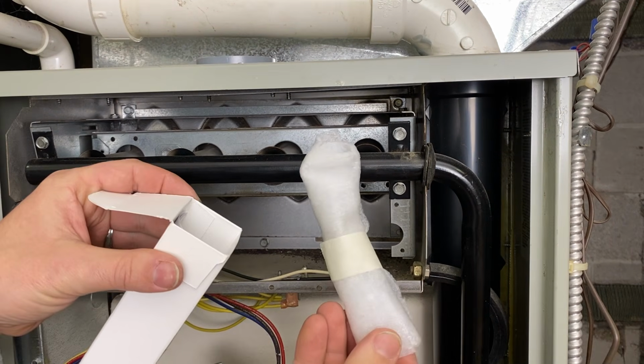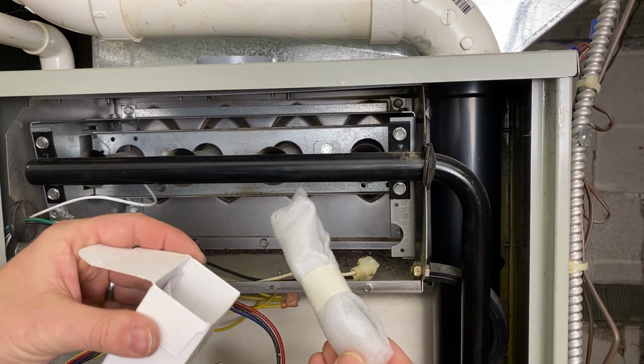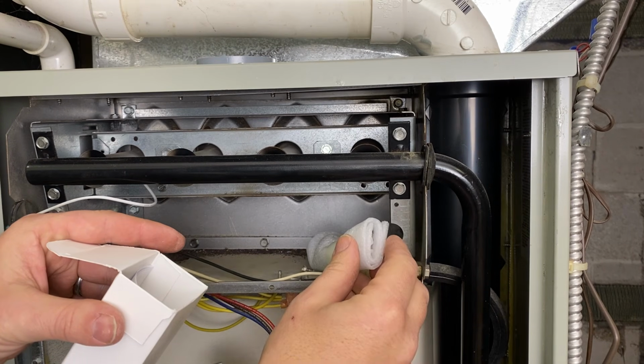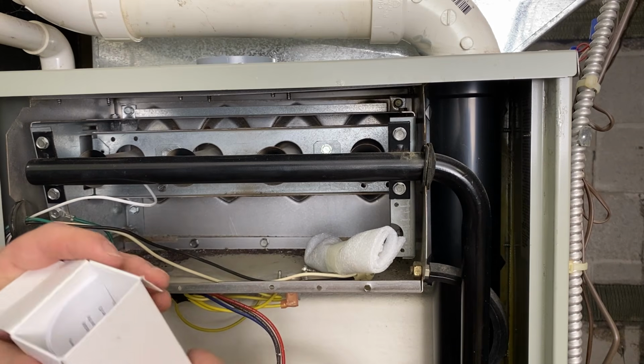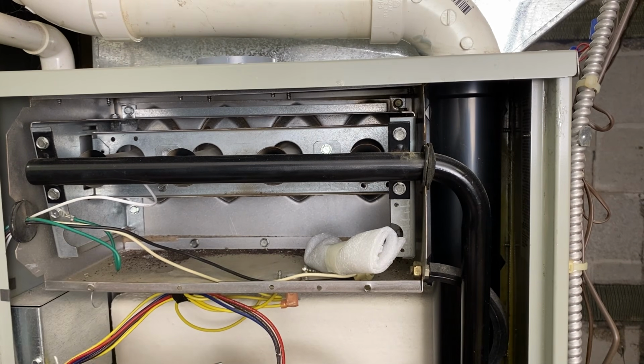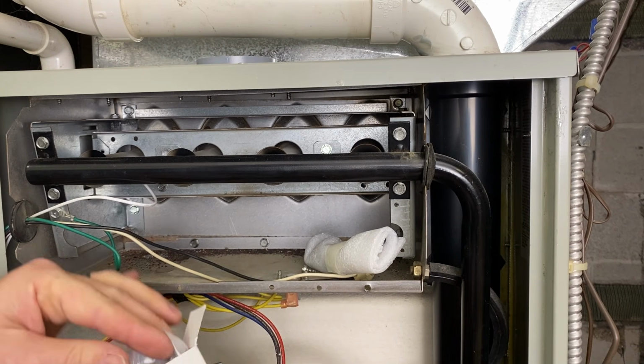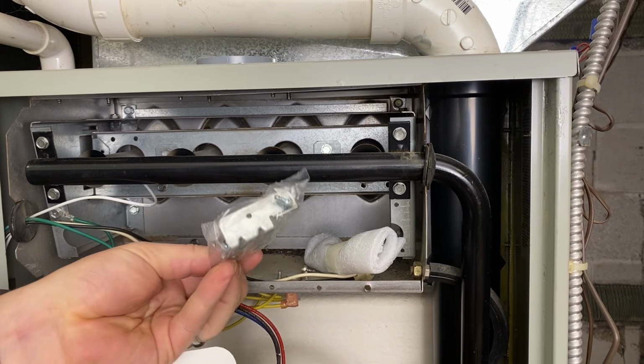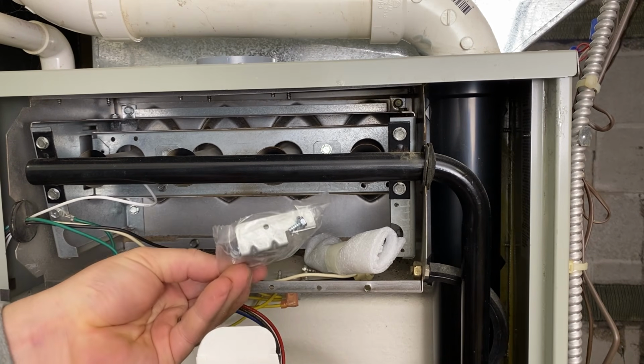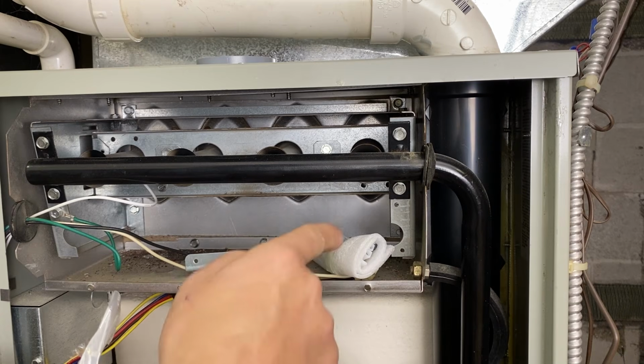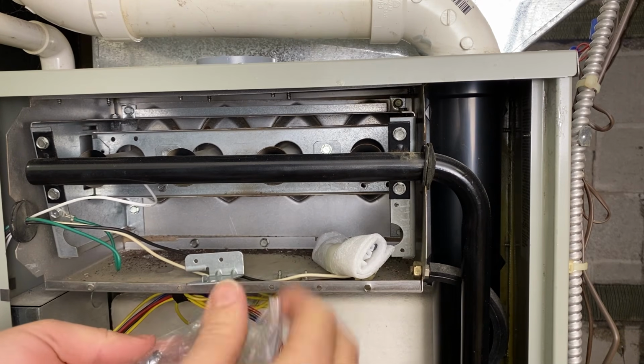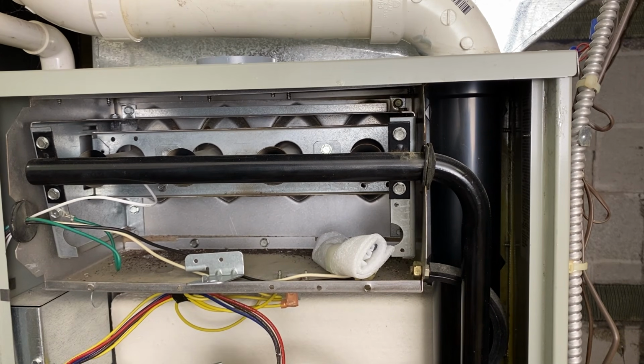So one thing to note with the hot surface igniter is that it is a very sensitive part. You don't want to touch it with your fingers to get any of the oils from your fingers on it, because it can actually cause it to have a hot spot on it, which will burn it out quicker. So this did come with a new bracket. Maybe we'll just use a new bracket, why not? While I'm in here, I'll take a vacuum also and just clean out some of this debris that's in here.